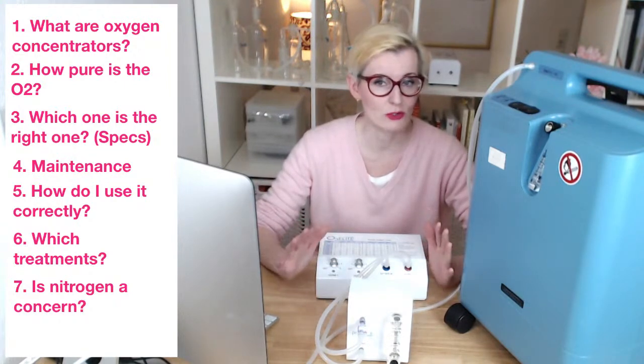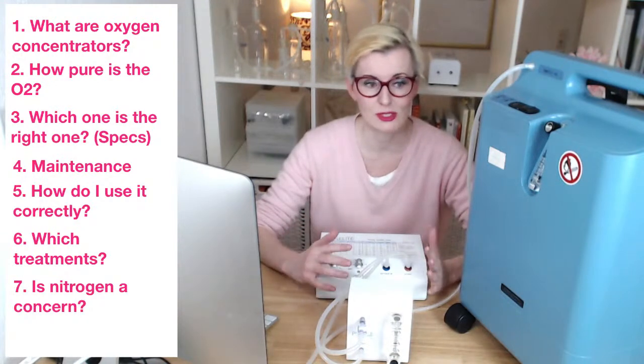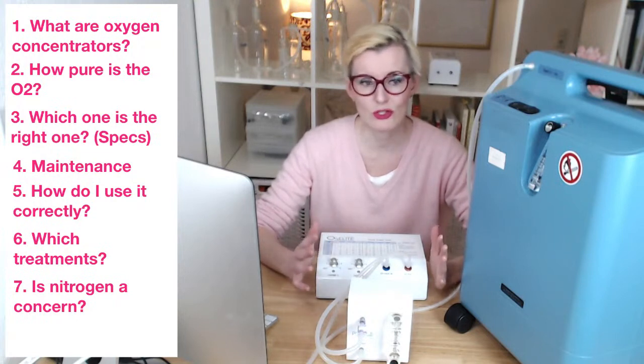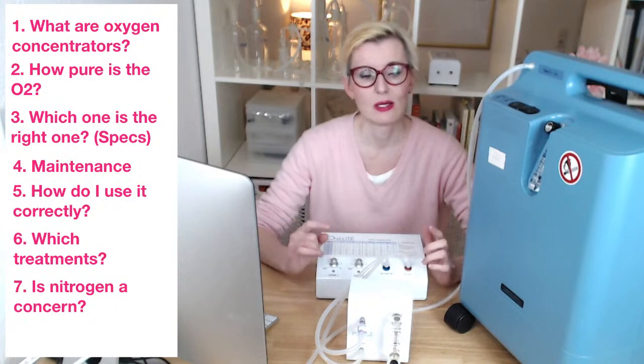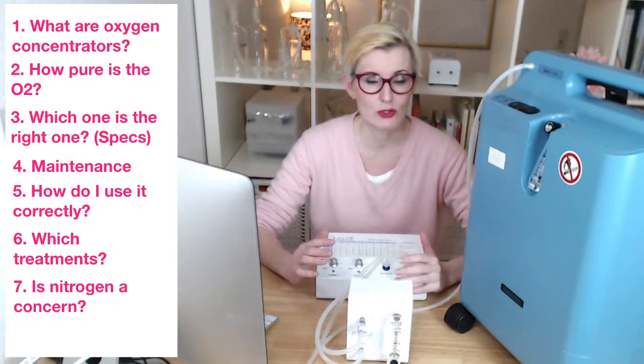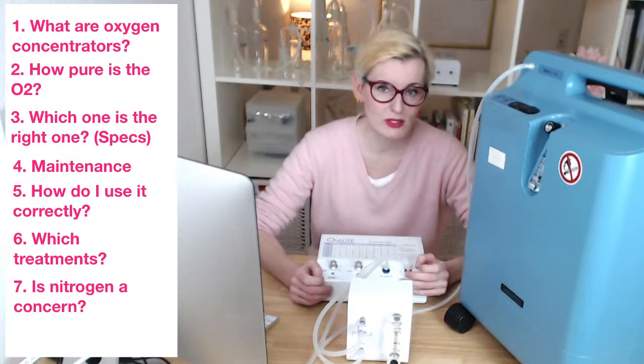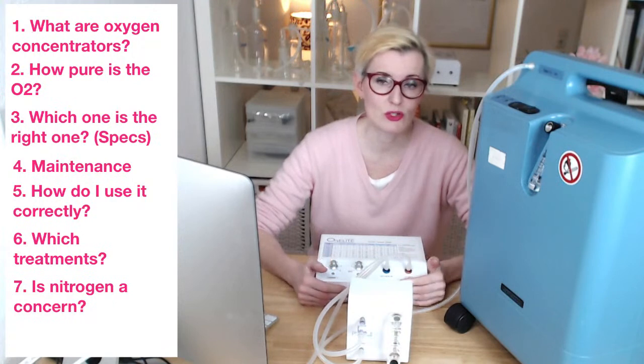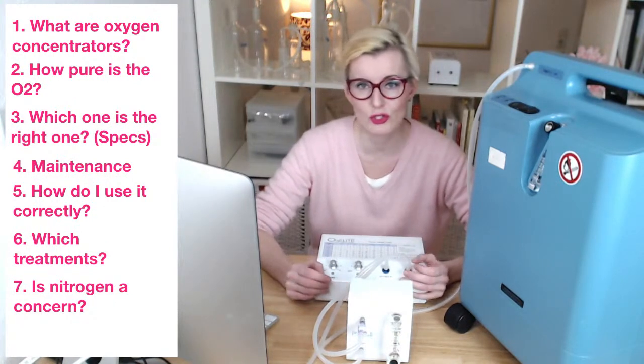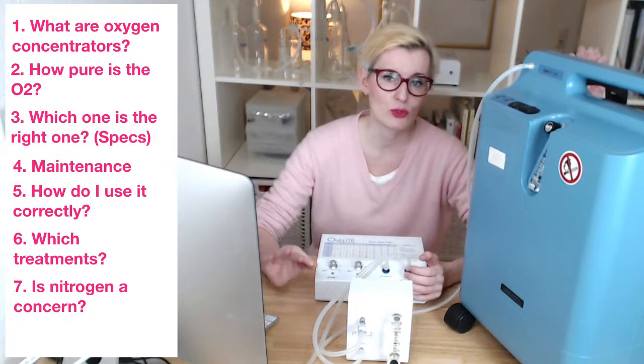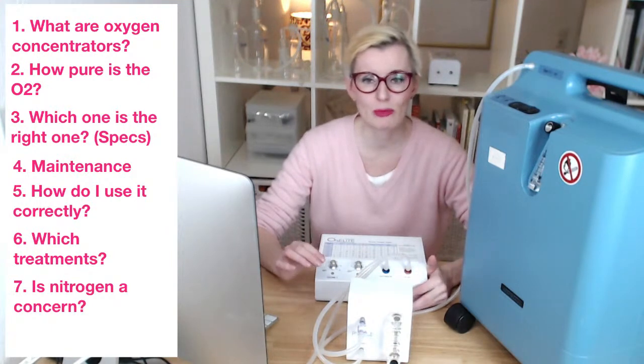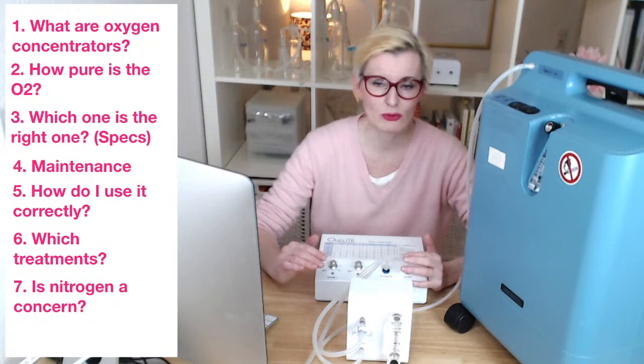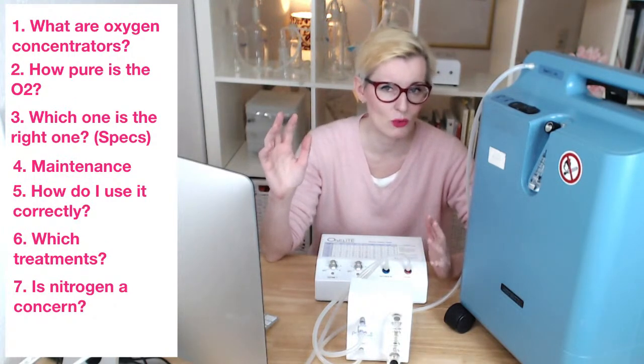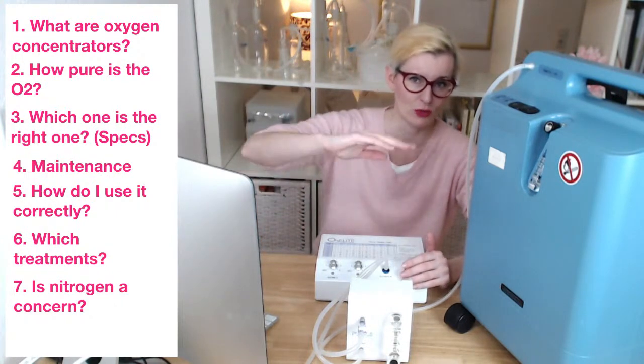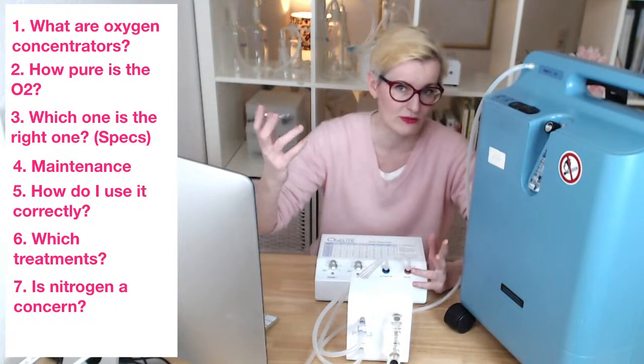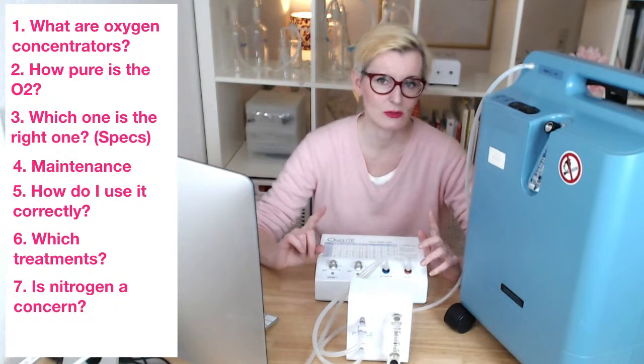So oxygen concentrators are a great alternative to oxygen tanks. They don't need to be refilled as long as you have power supply. You have oxygen, they need minimal maintenance, but you need the proper oxygen concentrators. So don't go for those portable ones, because the oxygen purity that they produce is not high enough. You need to look for something that produces oxygen of at least 90% at a flow of 2 liters per minute. Those also should not be pulsed oxygen concentrators. Some concentrators are sold as pulsed machines. I'm not quite sure what that means. I think it's not a constant oxygen flow, but it comes in pulses or waves, I believe. Those are not adequate for ozone therapy.